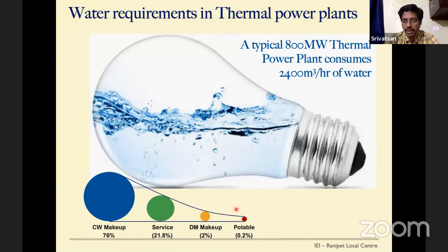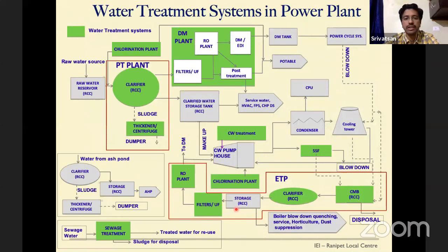So next we go on to how we treat it. This is a typical diagram of a treatment system and water cycle in a thermal power plant. Raw water comes from the raw water source and goes to the raw water reservoir. The source can be river water, borewell water, or sea water. Now I will discuss mostly brackish water, that is river or borewell water. Once it comes to the raw water reservoir, we have a clarifier system. This is called a pre-treatment plant. Here, the suspended solids present in the water are removed. Then this water goes to the clarified water storage tank. A portion of water is taken to the DM plant for treatment of dissolved solids. Another portion of water goes to the cooling water cycle.